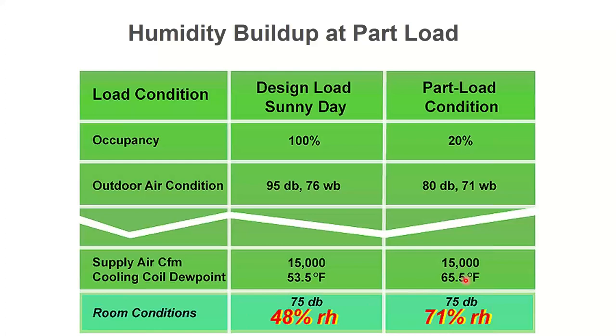How might that help? Well, if I have a standard package unit designed for maximum occupancy, obviously designed for a hot day, in this case it's 15,000 CFM. I selected my coil for a 53 degree dew point. My thermostat is set for 75 degrees in this space. That results in a 48% relative humidity. Everything's wonderful. But if it's not fully occupied or it's not a design day outside and I still move the 15,000 CFM, it's going to cause me to have to cycle this unit to maintain the 75: on, off, on, off. Whereas over here it was running constant.